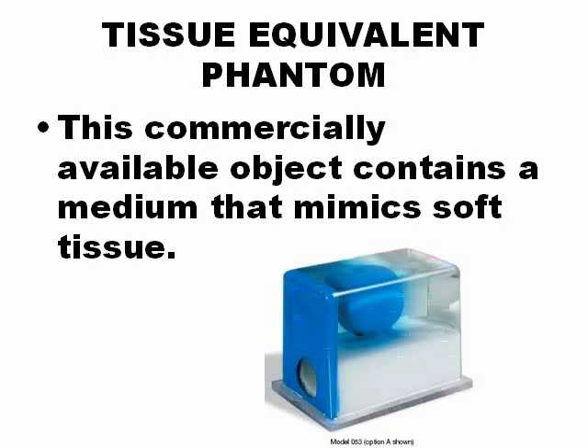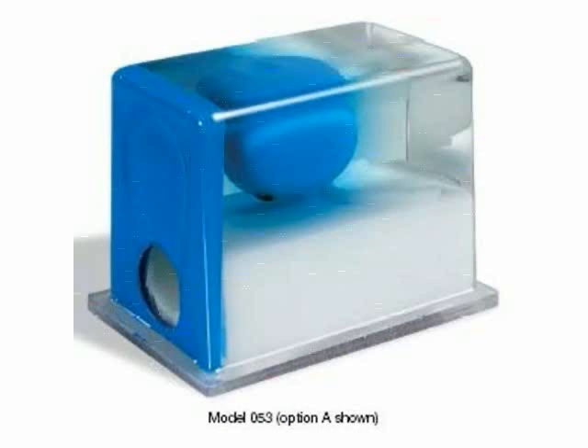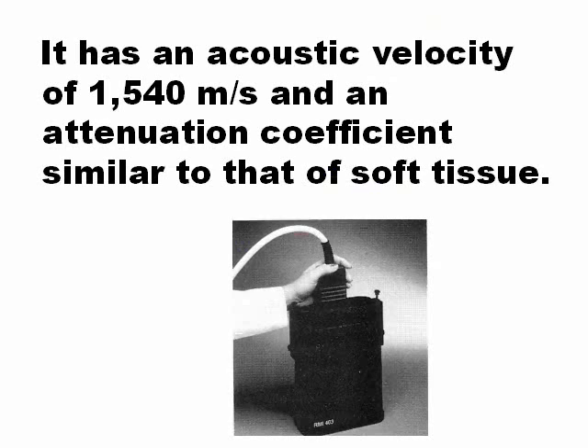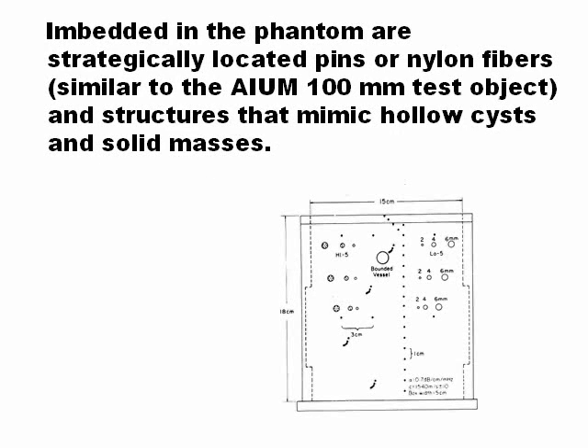The other phantom is the tissue equivalent phantom. In the example, you have one tissue equivalent phantom that is made to mimic the prostate. This commercially available object contains a medium that is similar to soft tissue, with the same propagation speed and the same attenuation coefficient as soft tissue. This is to study the prostate. It has an acoustic velocity of 1,540 meters per second, and the attenuation coefficient is similar to soft tissue. Inside the phantom, exactly like the other, there are structures that mimic cysts, hollow areas, and other things that are real in the body.